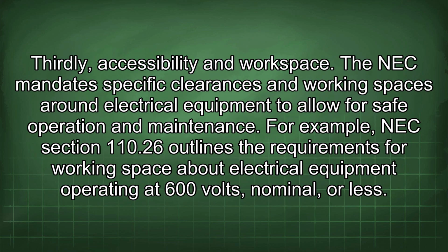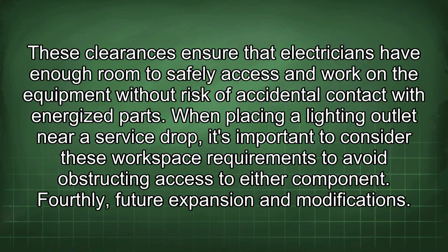Thirdly, accessibility and workspace. The NEC mandates specific clearances and working spaces around electrical equipment to allow for safe operation and maintenance. For example, NEC Section 110.26 outlines the requirements for working space about electrical equipment operating at 600 volts, nominal or less. These clearances ensure that electricians have enough room to safely access and work on the equipment without risk of accidental contact with energized parts. When placing a lighting outlet near a service drop, it's important to consider these workspace requirements to avoid obstructing access to either component.